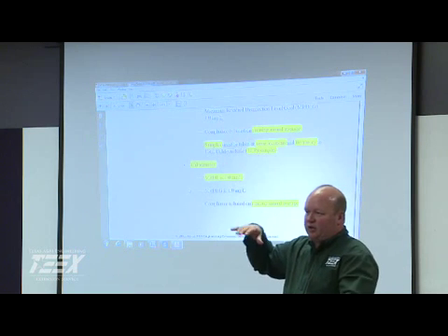Free chlorine, we've already talked about. MRDL is 4. Looking at a running annual average, you've got some people that are a roller coaster, so they're really high and they're really low. And if you can get that continual feed, some regular feedback monitoring going on, you can even that out and have a much nicer disinfection profile over time.